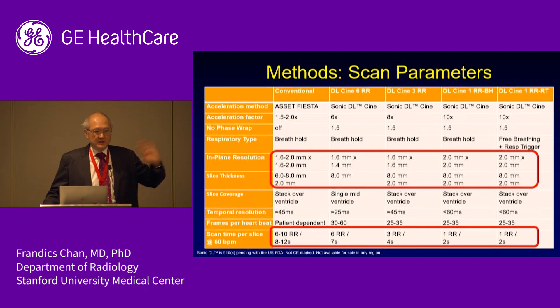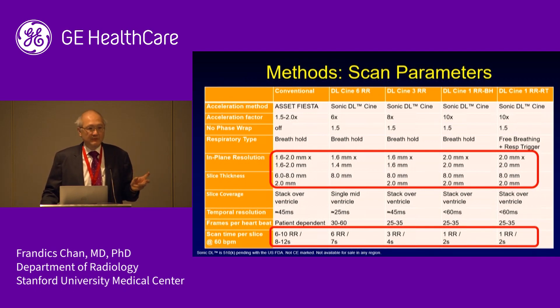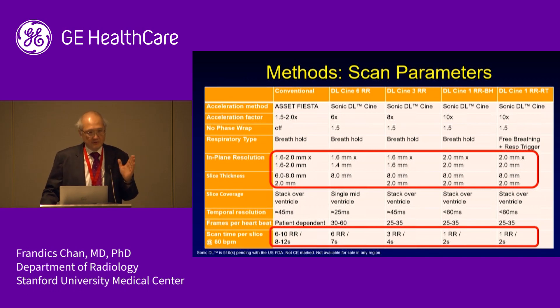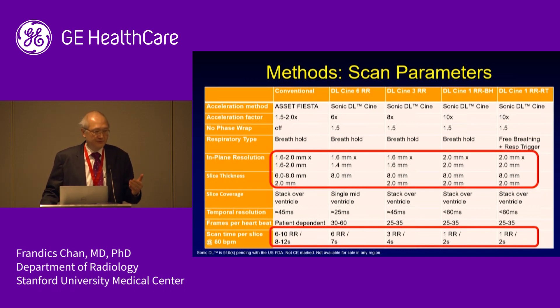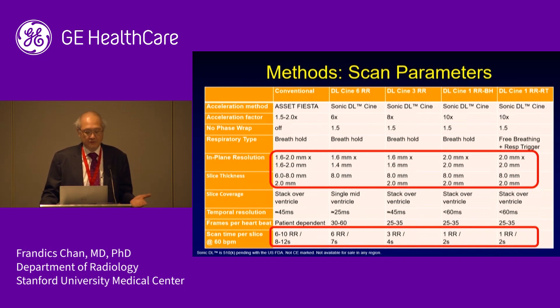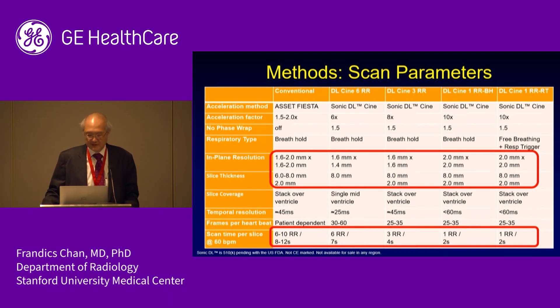The resolution is preserved across all tests — we keep that constant and allow the scan time to vary. Typically with the longer RR acquisition the acquisition time is going to be longer, but they span anything from two-second acquisitions to about ten seconds.